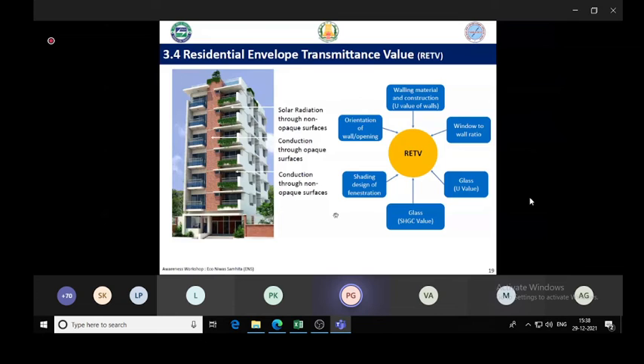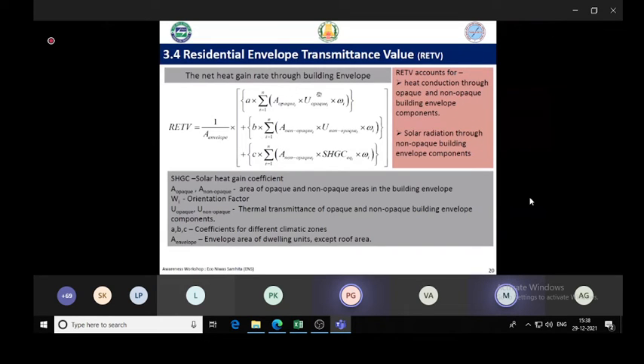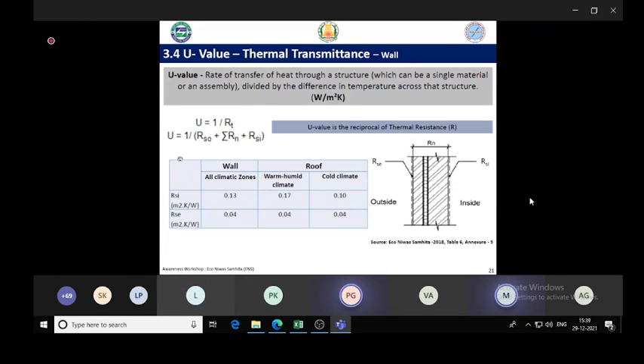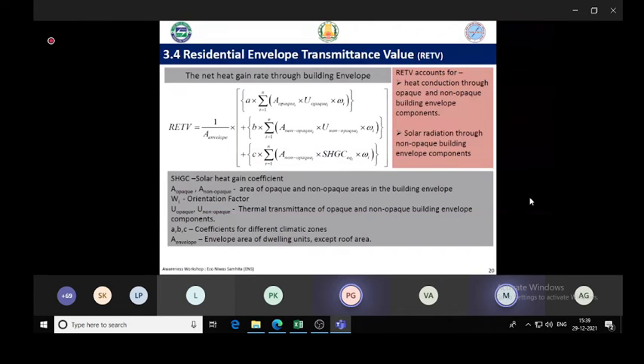And how is it done? So this is the formula to calculate RETV. You don't have to actually do the calculation. Again, as I said, the online tool can do the calculation. We need to enter the values like what is the area of my wall, what is the area of my window, what is the U value, and what is the SHGC, as well as what is my orientation. So based on this, the RETV will be calculated. And this RETV should be less than 15 watt per meter square Kelvin for achieving compliance.